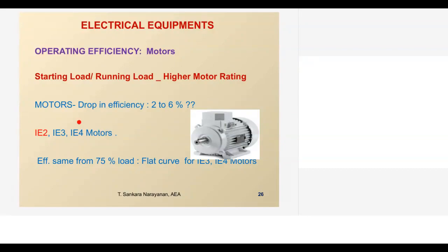And we are again going to international standards, IE2, IE3 and IE4 motors. So we will also see what is the advantage of this. Compared to IE2, the new motors which are coming will have a flat curve of efficiency. So between 75% load to 100% load, there is no drop in efficiency. Even at a lower load, if the efficiency is dropping, the drop is less. We will see different parameters.